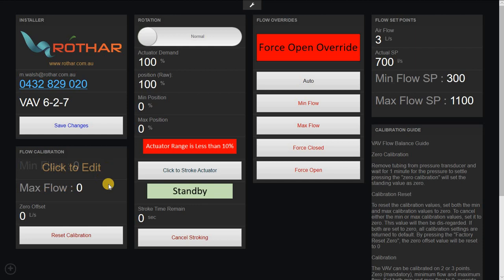Over here, the flow calibration, this is where they'll enter their values. So if they read a flow of 1100 litres, in the max flow they put in 1100, and that's how you calibrate the flow sensor. If they wanted to, they could also set that to minimum flow and set the min flow point, providing a 3-point calibration at 0, min flow and max flow. If they've buggered it up, or if this is a new install, just reset the calibration. It'll force these points back to 0, allowing you a clean slate and just providing a straight pass through of the flow readings.